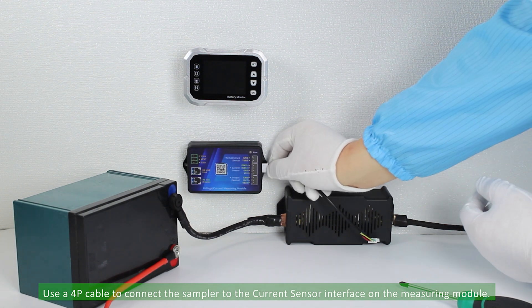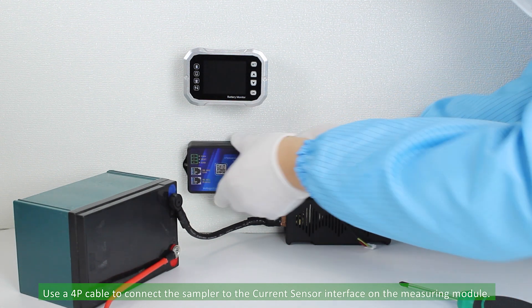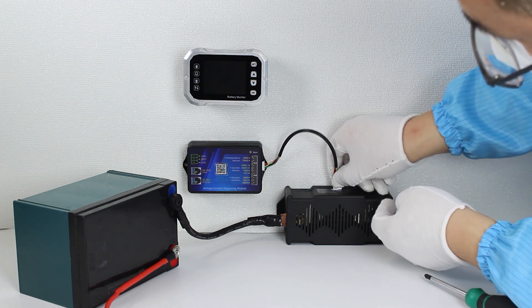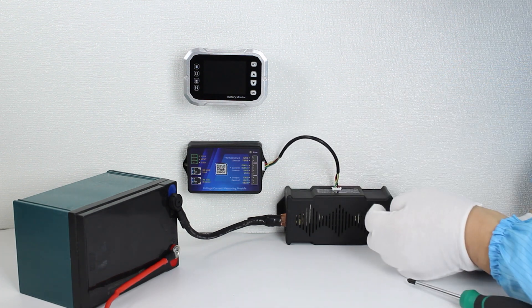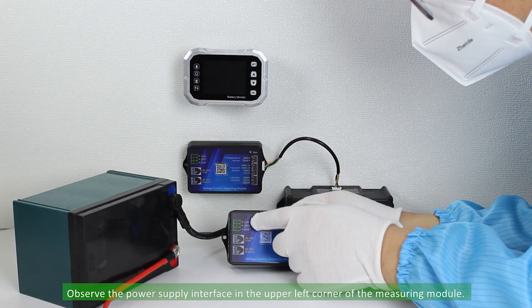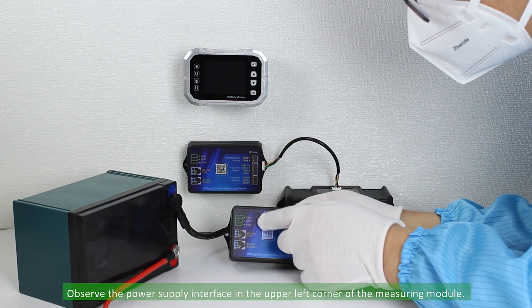Use a 4P cable to connect the sampler to the current sensor interface on the measuring module. Observe the power supply interface in the upper left corner of the measuring module.